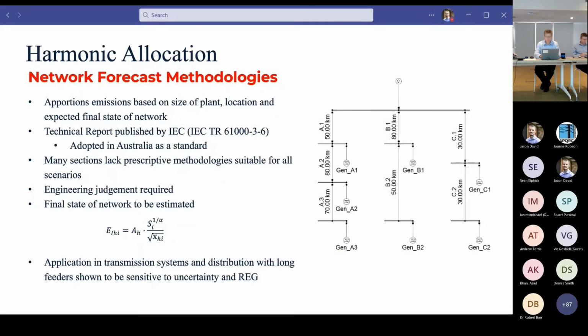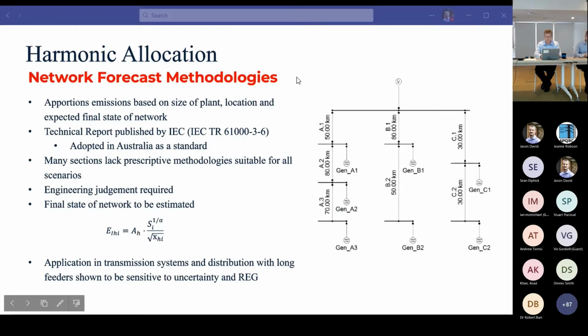To put it into an example, if we've got a network such as we have on the right hand side, a very simple radial network with a couple of long feeders, the NSP may make a couple of assumptions of where distorting loads may ultimately exist on the network. Using this assumption, it develops a harmonic allocation constant and will then calculate the allocated emission current limit to each connecting installation based on this assumption.